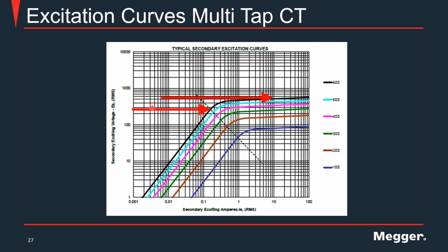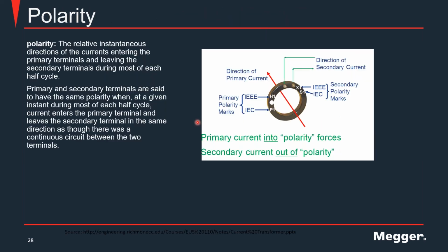The problem is that we see these graphs. It is a logarithmic graph, but we interpret it as a, let's say, linear graph. So we think that the difference between this point and this point being so close in the graph is very small, but it's actually very big. There's more voltage between this point and this point than the voltage between the start and the point where the saturation knee point is declared.